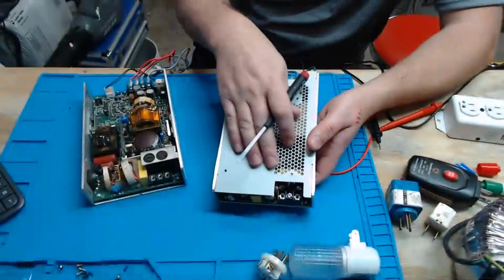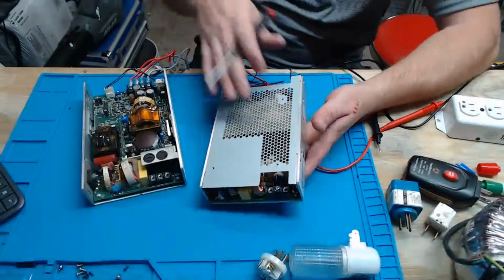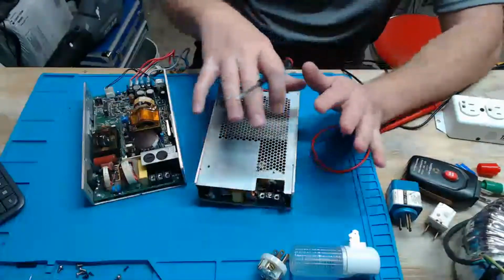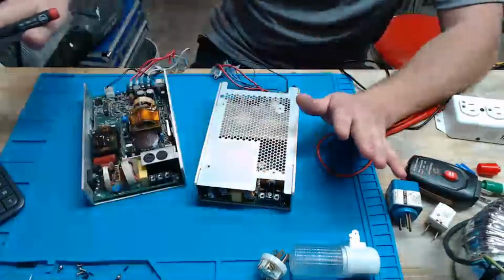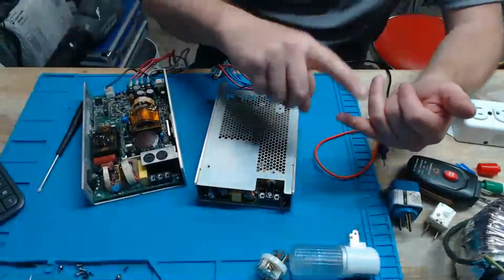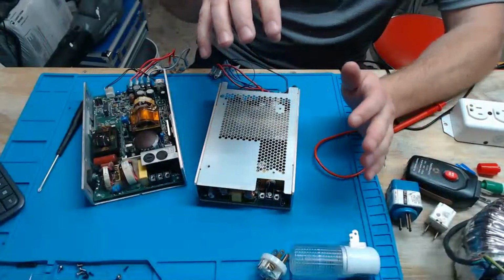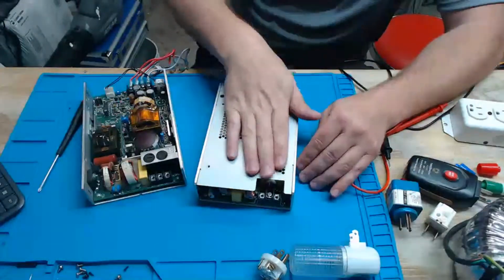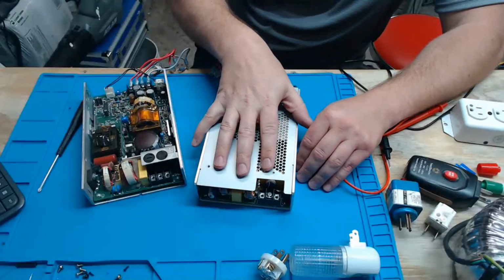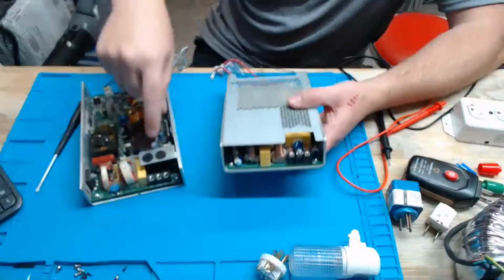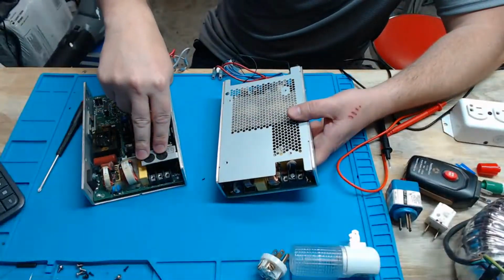Not only does it have the Faraday cage right here, which is a big indicator, a metal cage surrounding it for RF noise, because we don't want any RF noise getting out into the environment around EEG or EKG systems or anything. So there's a lot of shielding in a medical grade power supply, but chiefly we have line and neutral fused.